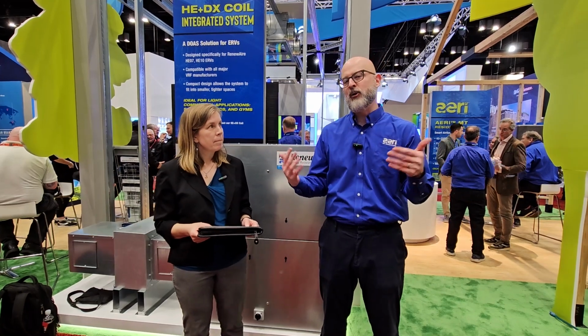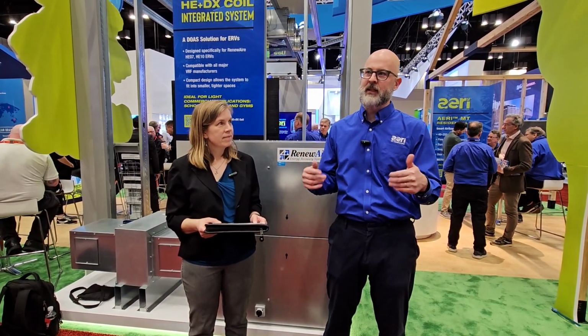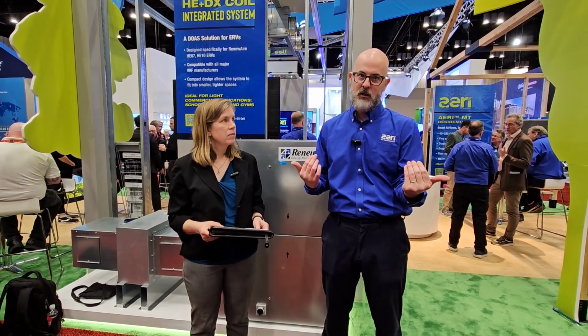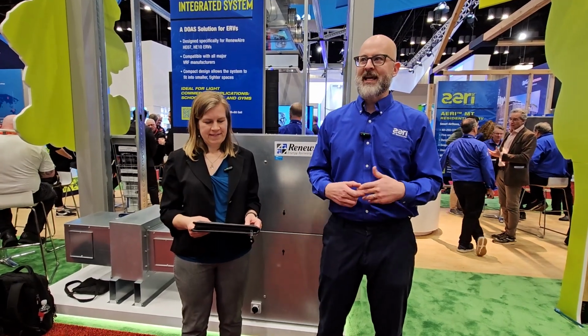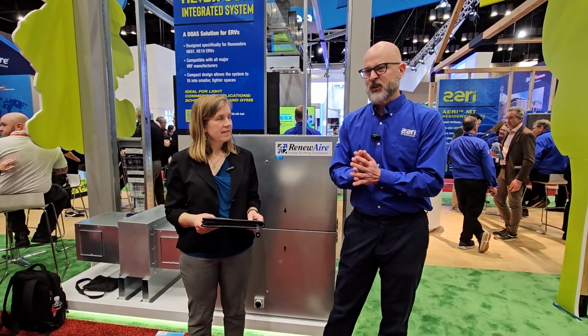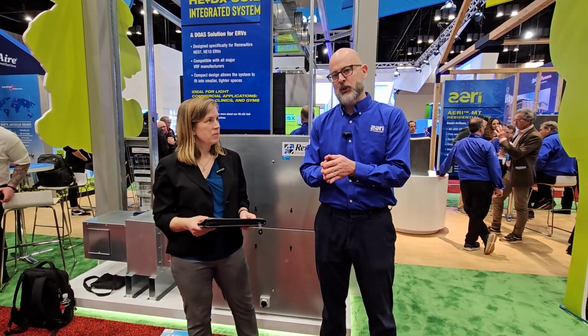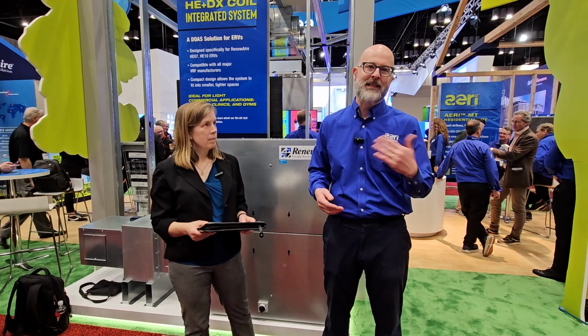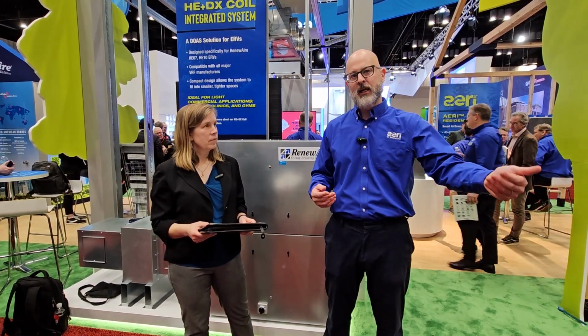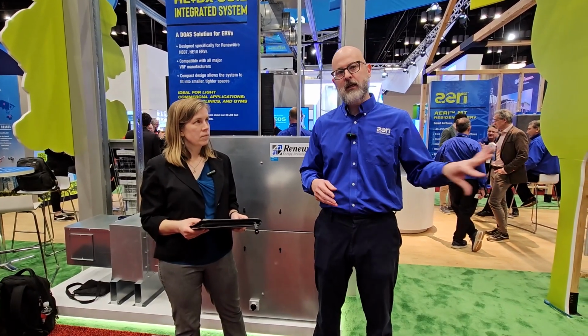Right. So decarbonization is tricky because we want to save energy, we want to save the planet, but simultaneously we need to keep people healthy, right? So as buildings get tighter and tighter, you're trapping all the contaminants inside the building. So you have to provide fresh air. Sorry, there's traffic around us. You have to provide fresh air, but then that's very expensive to condition, obviously. So that's why we include the plate heat exchanger to save energy and to transfer both sensible and latent energy from the exhaust air into the incoming airstream. So in the summer, we're rejecting the heat and humidity, and in the winter, we're warming the incoming air as well.